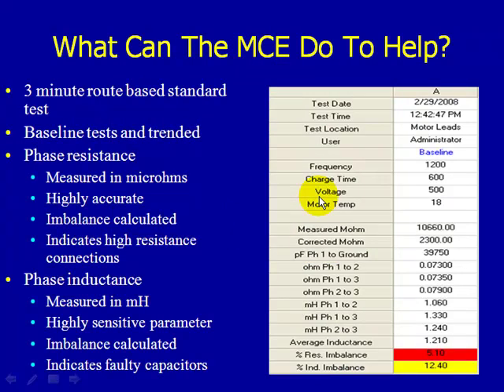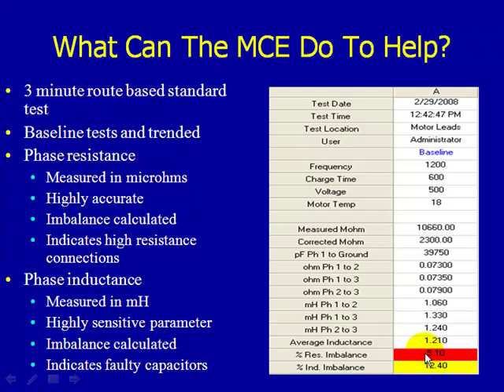How can the MCE help? This is a three-minute standard test that can be performed for acceptance testing or quality assurance. Within three minutes, we're testing resistance to ground, capacitance to ground, phase-to-phase resistance accurate to plus or minus 1% at the micro-ohm level, and phase-to-phase inductance. We also calculate percent resistive imbalance and percent inductive imbalance — highlighted in red or yellow if they exceed a threshold. Each test is stored in chronological order relative to a baseline, so any minor changes are annotated in the software to alert you for further troubleshooting.